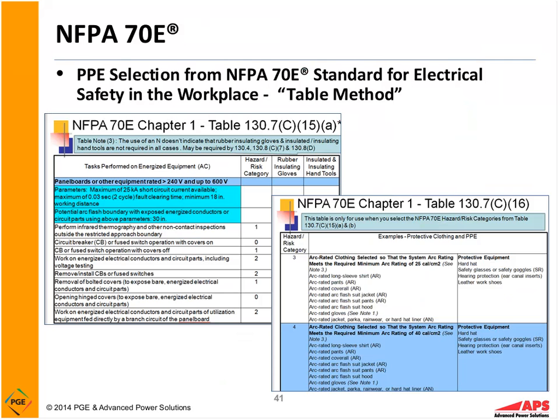If you look closely at the tables, you can see that there are some limitations. In other words, I have to find a table that matches up with the location I'm working at. I also have to make sure that I do not exceed the parameters that they provide in the table. In other words, they give a maximum short circuit current and breaker clearing or protective device clearing time.